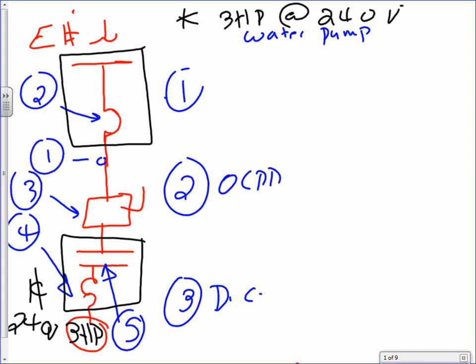One more time. I have a water pump. That's a powered electrical water pump. It's given by the manufacturer as 3 horsepower, 240, single phase, and it's powered from a panel. I need to size the circuit breaker, the branch circuit, the disconnect, the controller, and the overload, in this order. So when you have any motor, it doesn't have to be a water pump, it could be a fan, that's what you will be required to provide for the manufacturers to install this system. I'm going to give you a few seconds before I start sizing these systems.